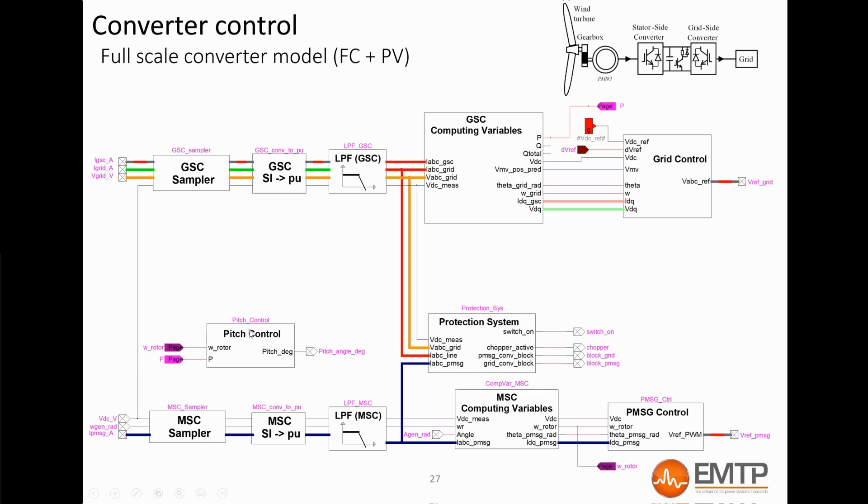The pitch control block limits the mechanical power extracted from the wind by increasing the pitch angle when the wind speed is above its rated. The protection system block contains cut-in and cut-off speed relays, low-voltage and over-voltage relays, machine-side converter and grid-side converter overcurrent protections, and DC resistive chopper control. The LVRT and OVRT functions are in this block. We will discuss this block in more details in another video.